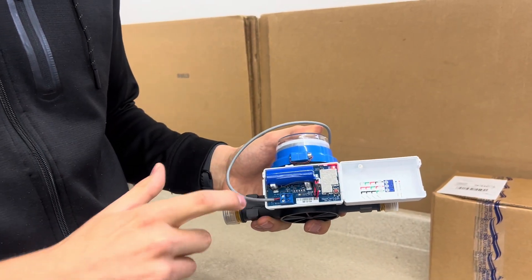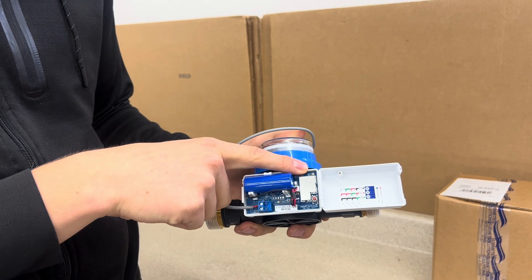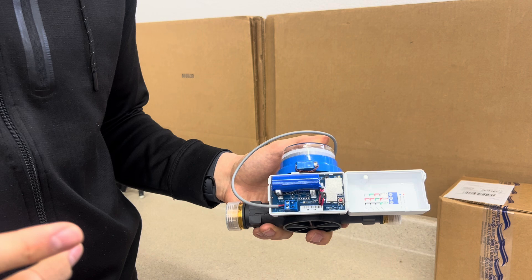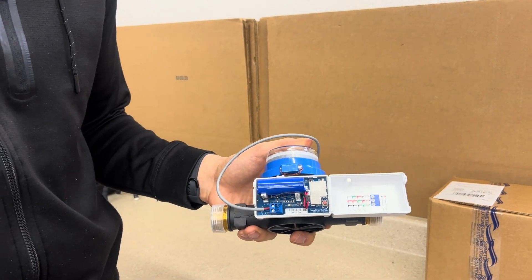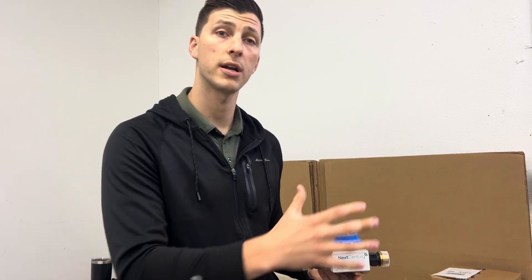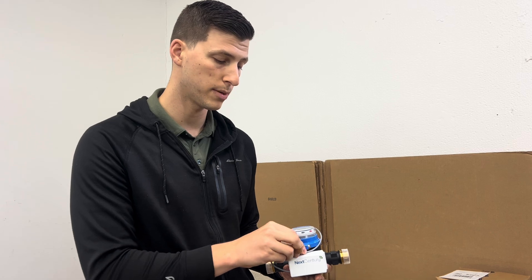With NextCentury, if this is connecting, this red light is going to blink and then it's going to respond after a couple seconds with a blue light, indicating that it's connecting to the wireless system. So that's a basic overview of the three portions of a meter transmitter set that you want to inspect to make sure that it's reporting properly.